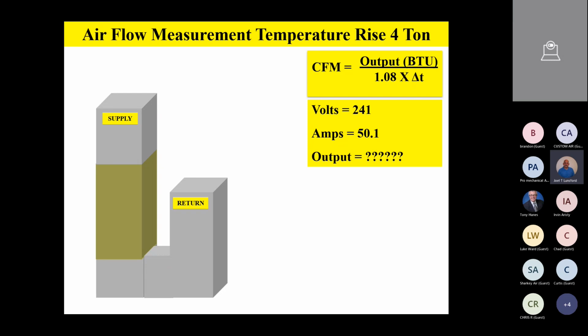So quick reminder, we take voltage times amperage. So 241 times 50.1. But hang on, we're not done yet. You multiply that times 3.414 to give us BTUs, output BTUs. So 241 times 50.1 times 3.414 gives me my output. If you poke it in on your calculator, you should have about 41,221 is what I have.